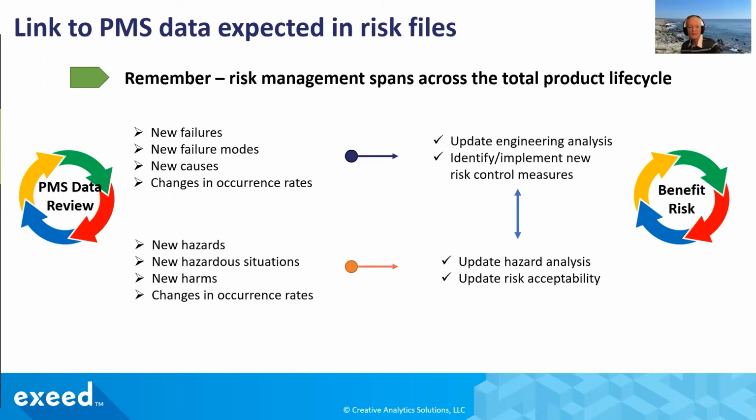Yeah, there's an ISO TIR that talks about this, which is 20416, I think, which talks about connecting the data from 13485 and 14971 for post-market surveillance. And it's a good guidance document. First revision, so it'll take a couple cycles for it to really be valuable, but it has some good information in it now.